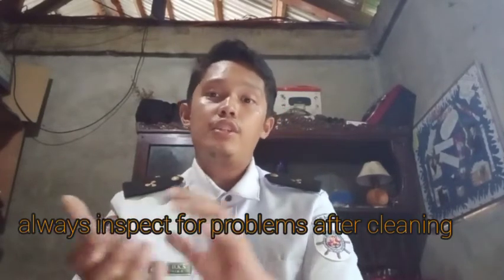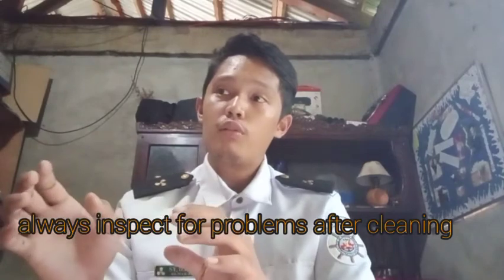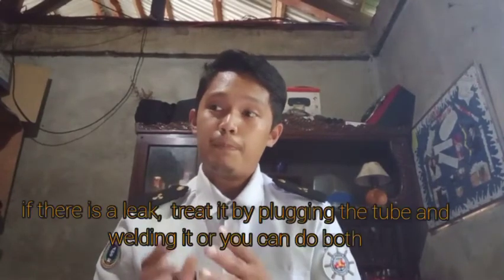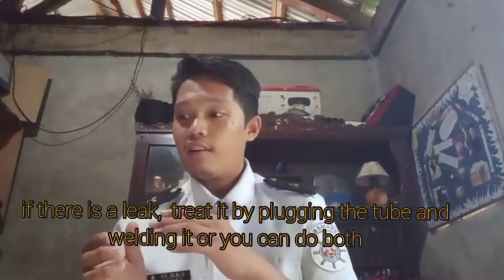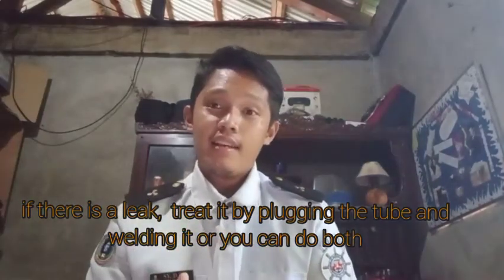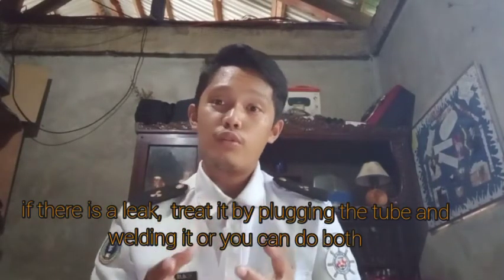After cleaning the tubes, you should remember to inspect if there is leakage on the tube, so that you can give solutions to that. If you find that there is a leak inside the tube, you should plug the tube, or do welding, or do both, so that the leakage will be solved. So the next is the plate type heat exchanger.